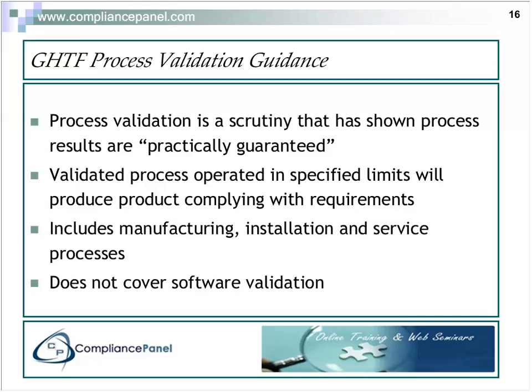One of the reasons for including installation is that in certain types of medical devices such as CT scanners, MRs, and other devices, part of the process in producing that product is the actual installation in the facility where it's going to be used. In that case, the installation process has to be validated as well, to show that we will guarantee that this product, which has been produced, shipped to the customer facility and installed, will in fact meet the requirements of that particular product. We certainly don't want to have overdoses of radiation to individuals because something went wrong during the installation.